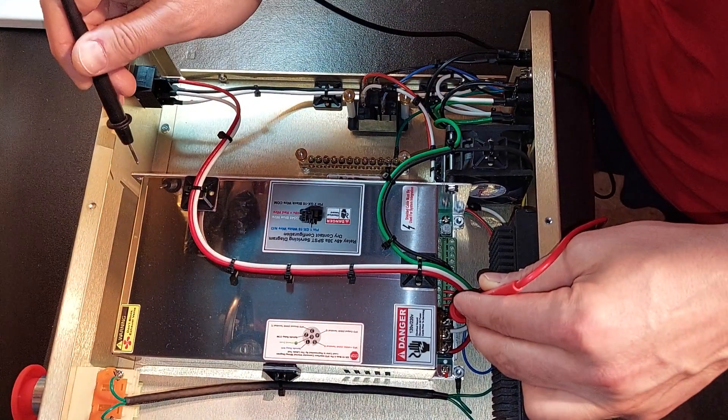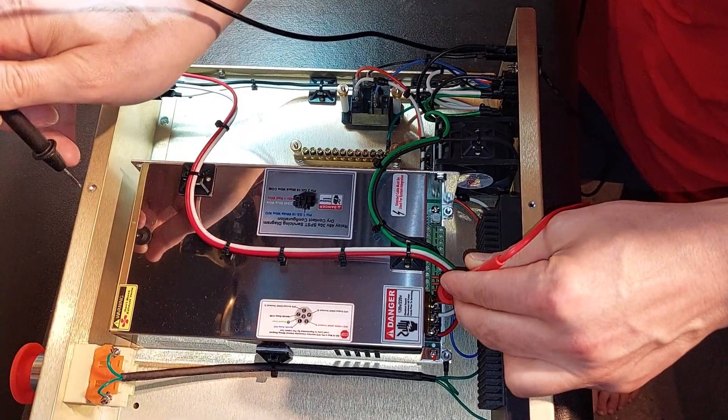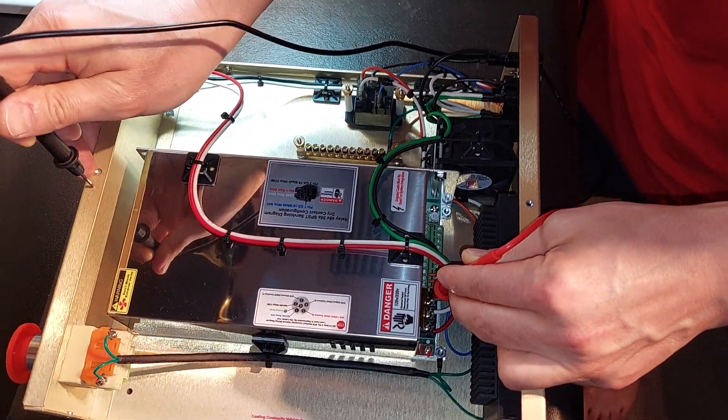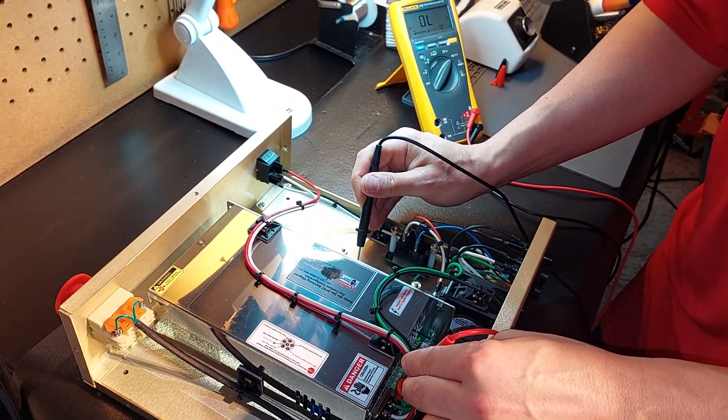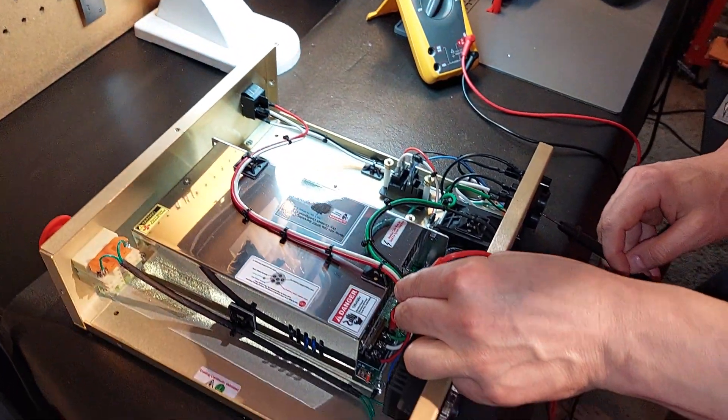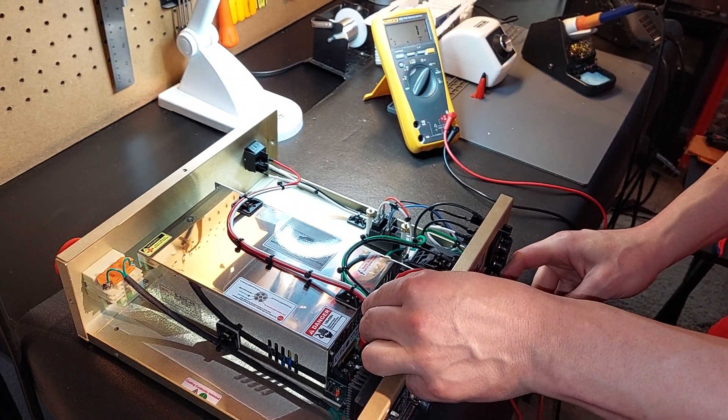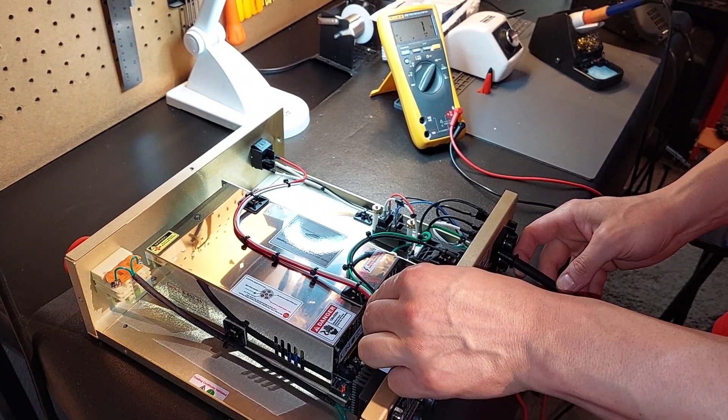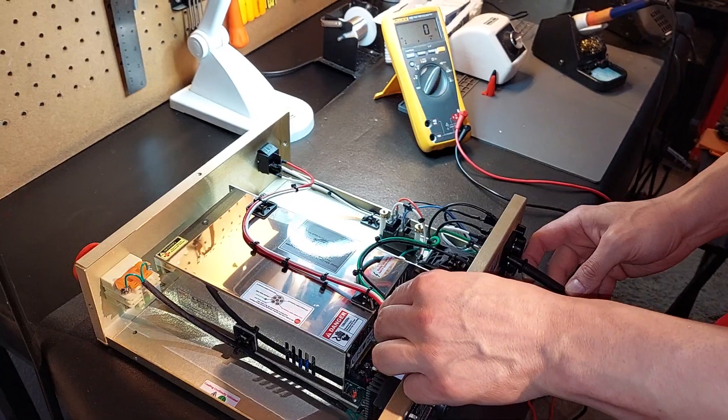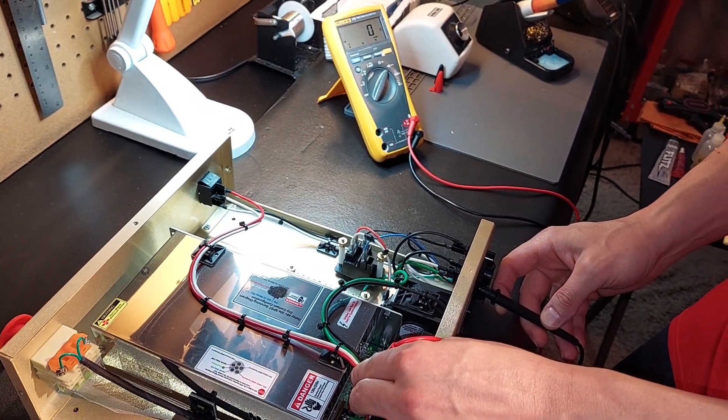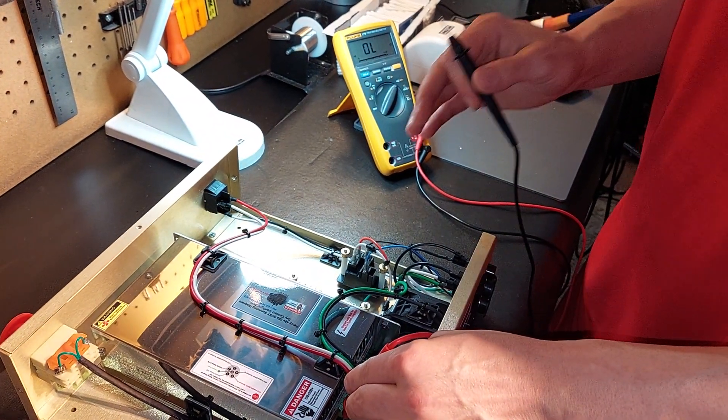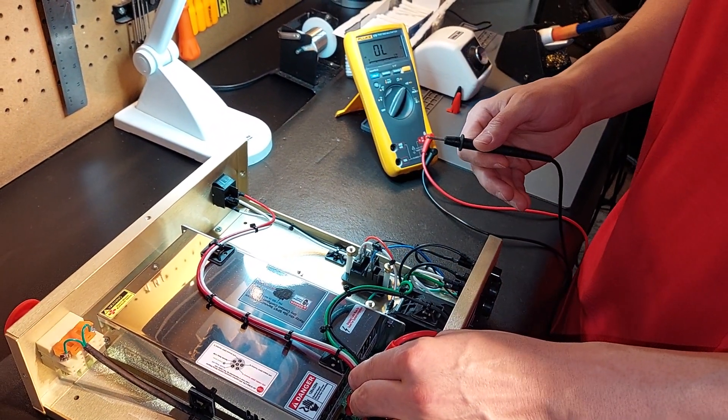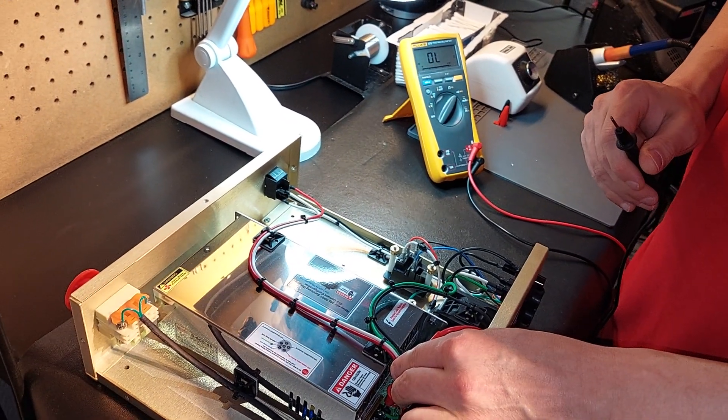That means the chassis of the power supply should be grounded, same location. Electrical enclosure grounded, same location. Ground bus bar grounded, same location. IEC power port grounded, same location. And then of course, whatever auxiliary port you have, grounded, same location. The lower the resistance, you see zero on that multimeter, that means that that ground is very low in resistance to actually dissipate EMI. That is what you're going for.